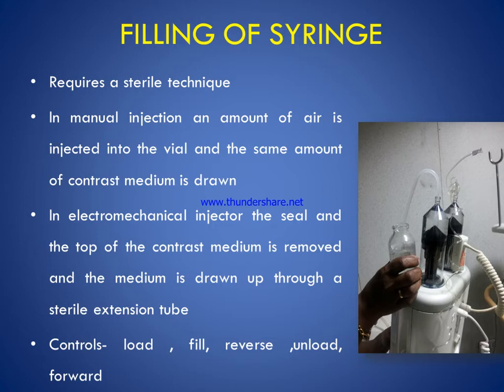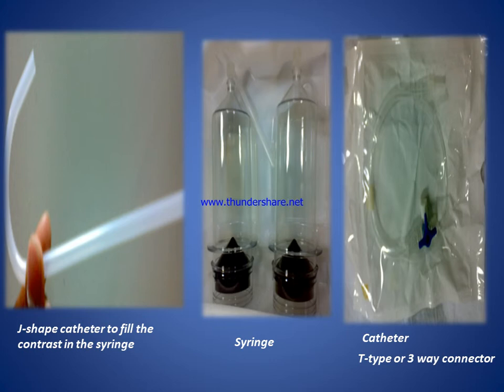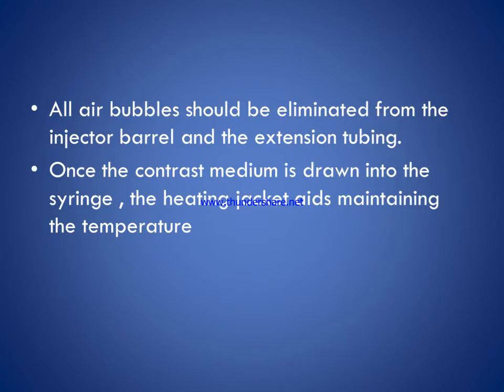Filling of the syringe is the procedure or technique to fill the syringe. A sterile technique is used. In case of manual injection, a certain amount of air is injected into the vial and the same amount of contrast medium is drawn in. In the electromechanical injector, the seal on the top of the contrast medium bottle is removed and the medium is drawn up through a sterile extension tube using controls such as fill, reverse, load, and forward. Equipment includes a J-shaped catheter to fill contrast into the syringe. All air bubbles should be eliminated from the injector barrel and extension tubing once the contrast medium is drawn in, and the heating jacket maintains the temperature.